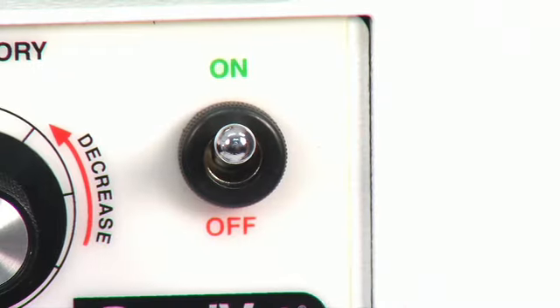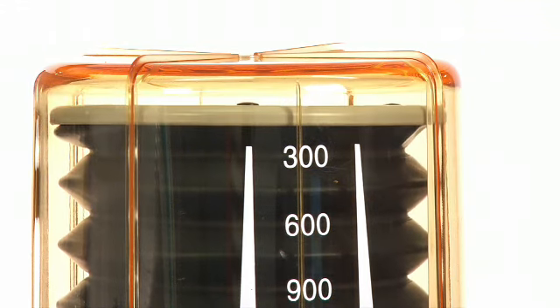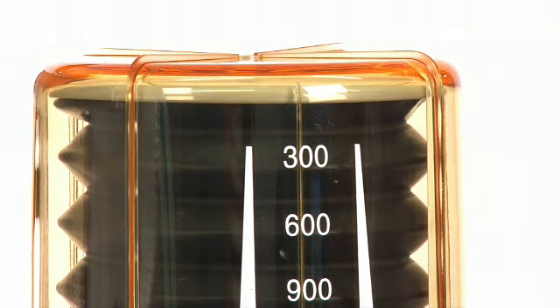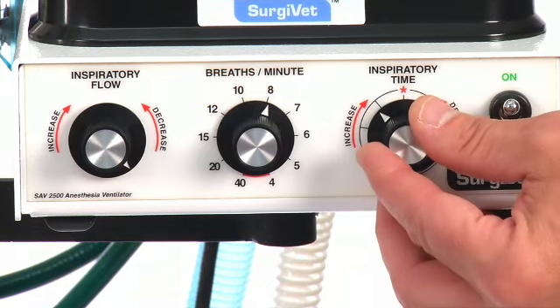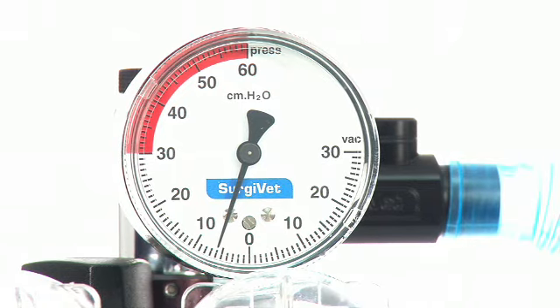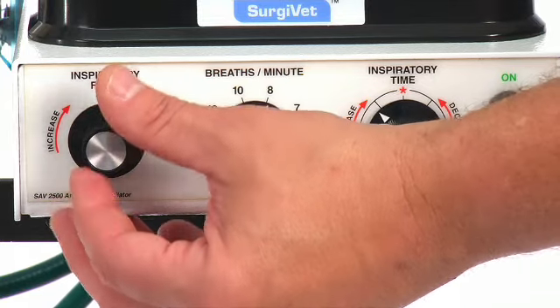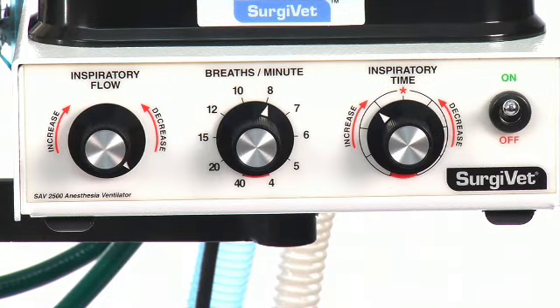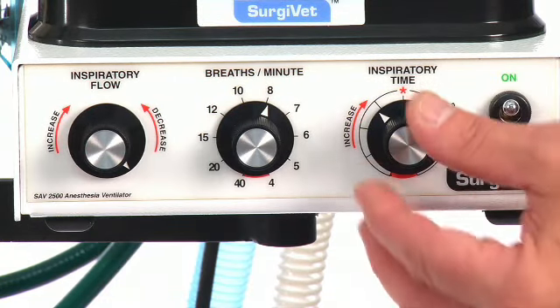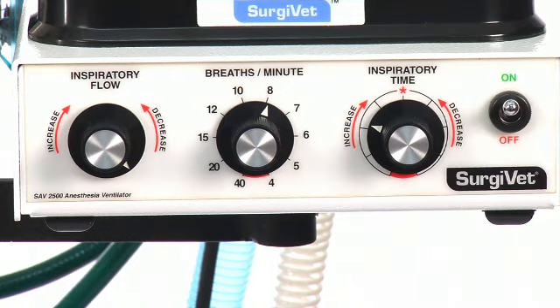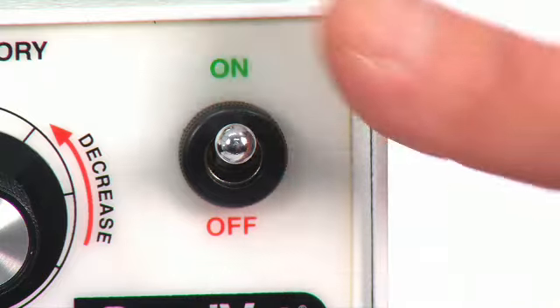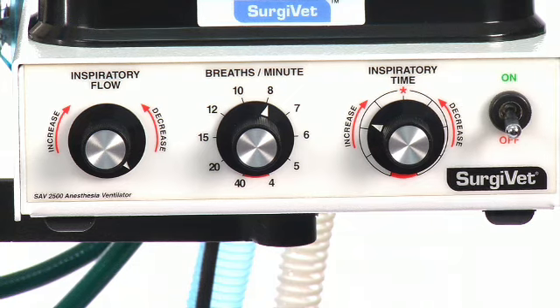Turn the ventilator on. You should hear the bellows fire but not move greatly. Increase the inspiratory flow very slightly and refer to the pressure reading on the manometer located on the anesthesia machine. Adjust the knobs on the ventilator to deliver the desired ventilation for the patient, determined by the attending veterinarian. Once this is determined and the controls are in the proper position, you can turn off the ventilator. The machine will hold these settings until the time you need to attach the patient.